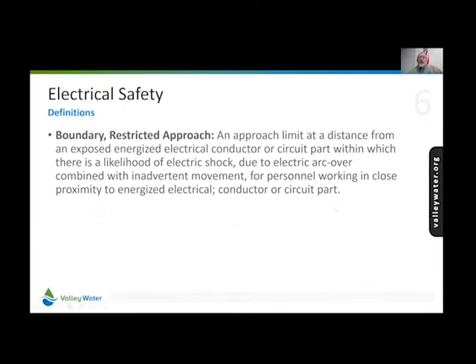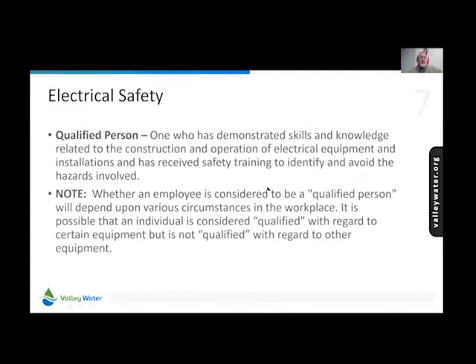A restricted approach boundary is an approach limit at a distance from an exposed energized electrical conductor or circuit part within which there is a likelihood of electric shock due to electric arc over combined with inadvertent movement from personnel in close proximity to energized electrical conductor or circuit part. So basically when you're sticking your hands in the panel, that's what that boundary is.